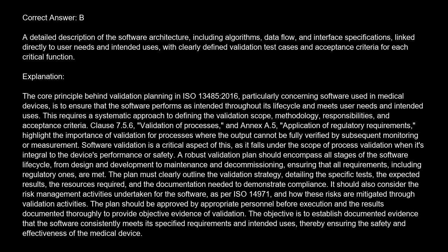The plan must clearly outline the validation strategy, detailing the specific tests, the expected results, the resources required, and the documentation needed to demonstrate compliance. It should also consider the risk management activities undertaken for the software, as per ISO 14971, and how these risks are mitigated through validation activities.